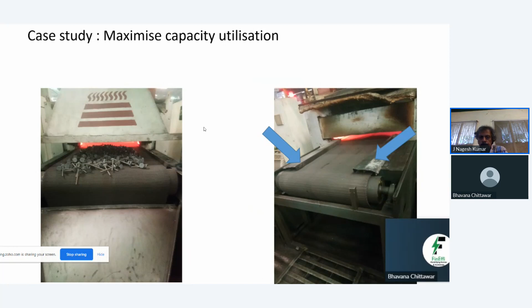This is a case of a paint shop in a heavy equipment and machinery manufacturer. Materials come into this paint booth, with an air supply fan on top with filters supplying air to the paint shop for painting. So there's a ventilation system: a supply fan blowing air from the top, and an exhaust removing the paint fumes through two 275 kilowatt fans. The heavy equipment keeps moving along the conveyor. There's a top port flush-off fan and another fan which blows off, allowing partial drying before it goes into the oven. So this is the system.